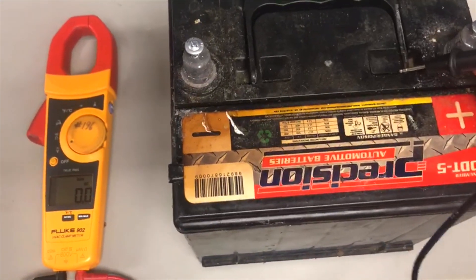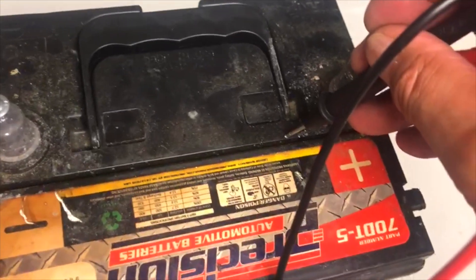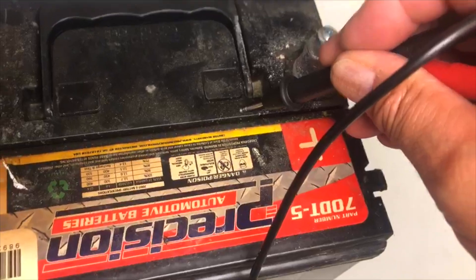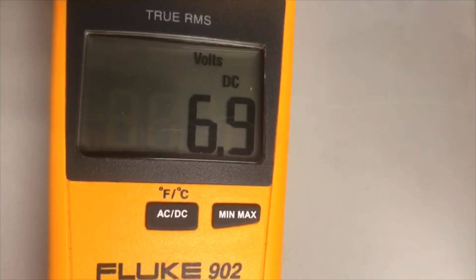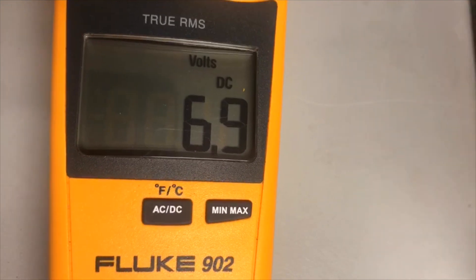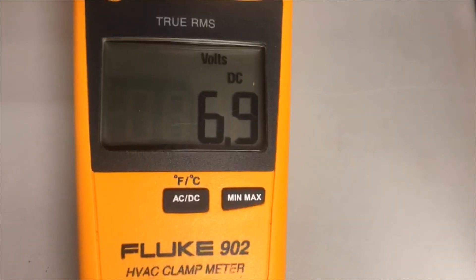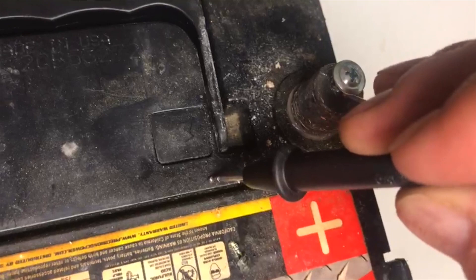If we go from the terminal here to the casing, the casing is made out of plastic. We're going straight to the casing. Because of this, we see that we're reading 6.9 volts on there. That tells me that this battery is losing some voltage constantly going straight to ground. We should not get anything.